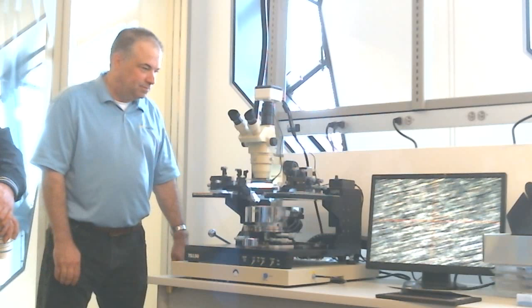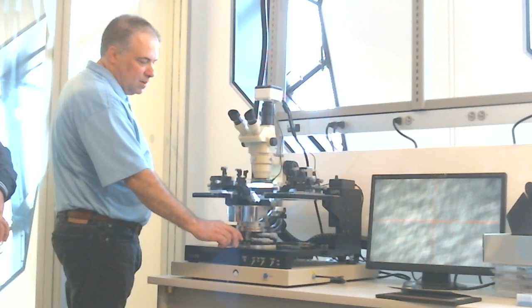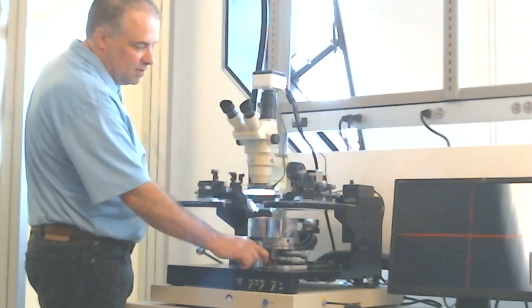If I keep going down a little bit further, you have the chuck stage. The chuck stage is also controllable in X, Y, Z, and theta. The main control is this puck here. On the left of the puck, there's a push button that activates the air bearing, and this surface here is an air bearing surface. When I press the button on the left of the puck, it'll allow me to just float the stage around wherever I need to go, very, very quickly.